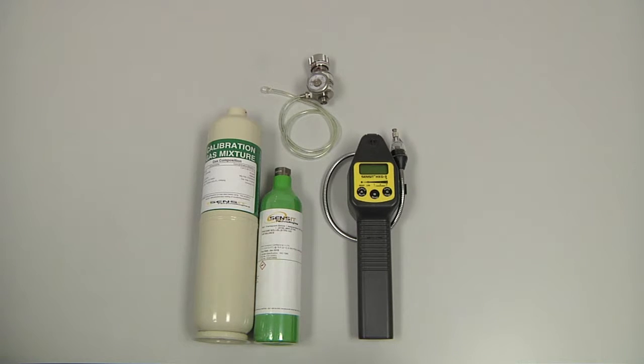To perform a manual calibration of the Sensit HXG3P, we will need the instrument itself, a regulator with cal adapter, and the calibration gas, which is 50% LEL methane, or 2.5% by volume, or alternatively, 50% LEL pentane, or 0.75% by volume.